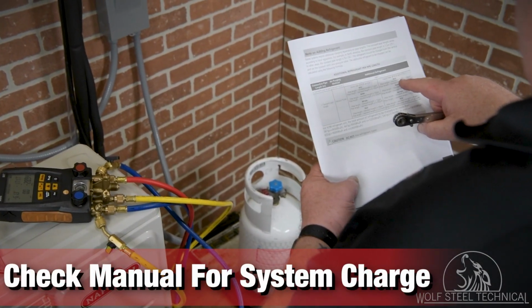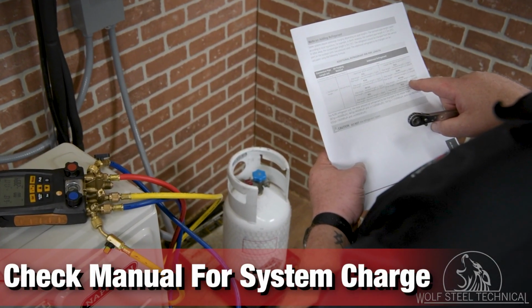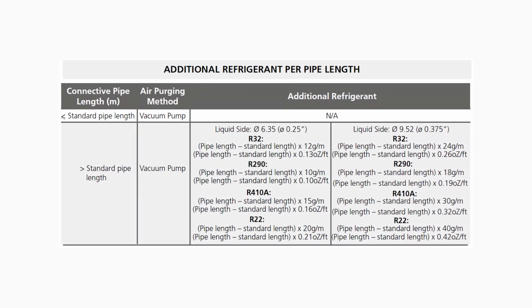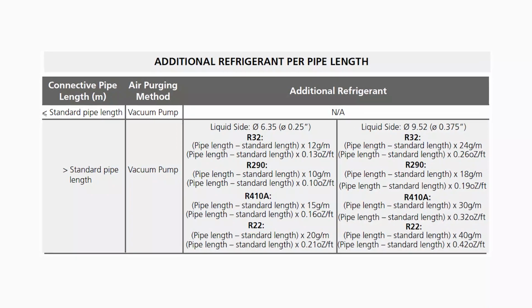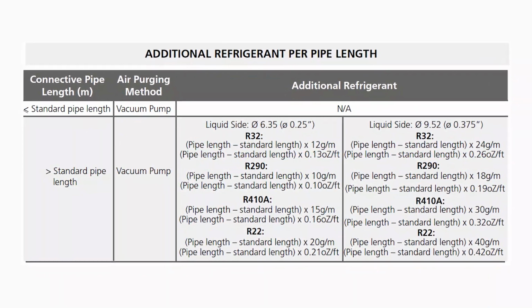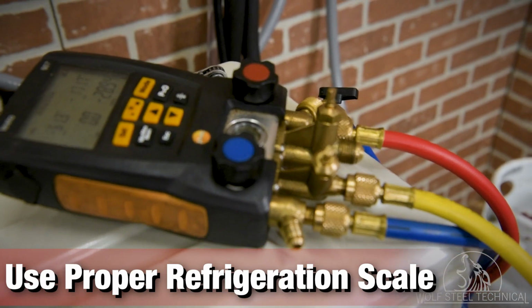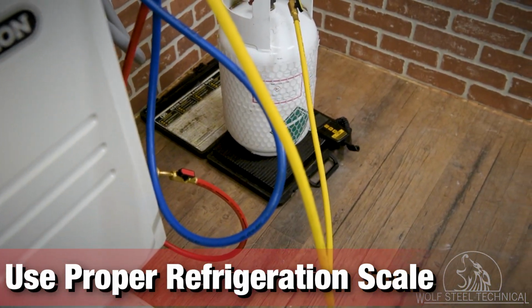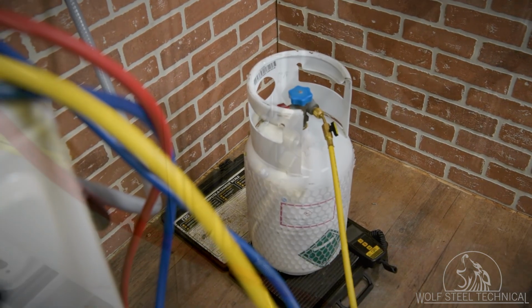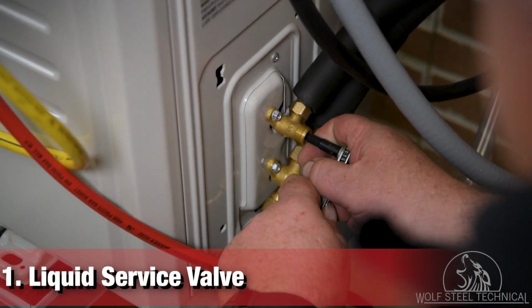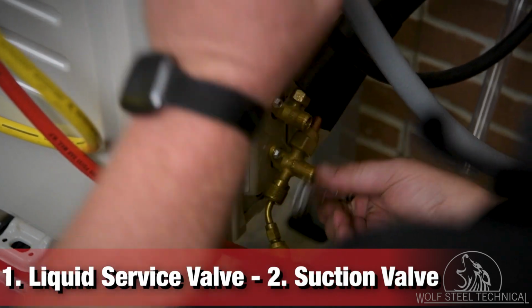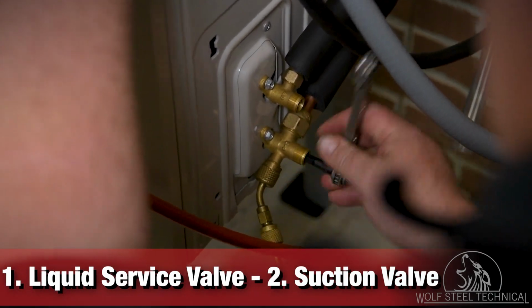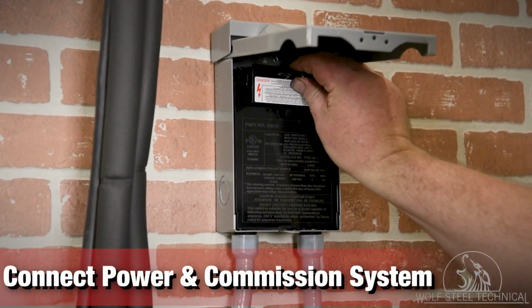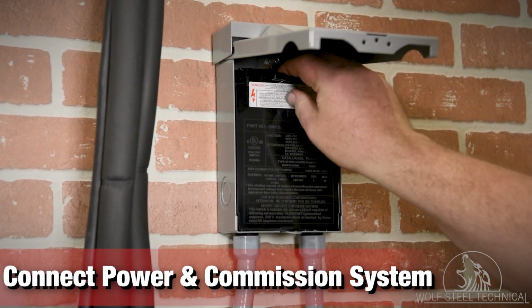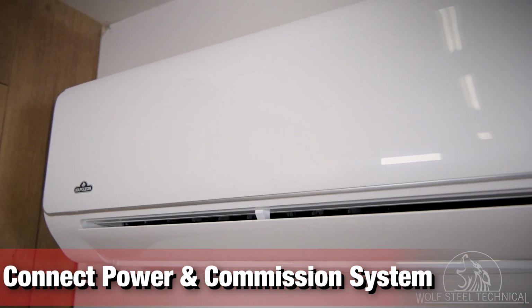Next, check the installation manual for acceptable line set lengths and factory charge in the condenser. Depending on the diameter of the liquid line, refrigerant should be added in ounces per foot, according to the chart in the manual. When adding refrigerant, use a proper refrigeration scale to measure the correct amount to add, as calculated. After the refrigerant is added, open the liquid service valve, followed by the suction valve. This allows the new refrigerant to mix with the factory-charged refrigerant. Once charged correctly, return power to the system, which was removed during electrical connections, and head inside to start commissioning.